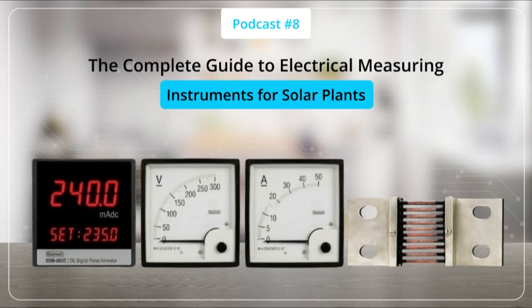To understand how much sunlight is actually available at a site, a pyranometer is used. It measures solar irradiance, the intensity of incoming sunlight, which directly affects how well the system should be performing at any given moment. Cable and system insulation safety is checked using an insulation resistance tester, often called a megger. This is critical both during installation and as part of ongoing maintenance. Thermal imaging cameras add another layer of diagnostic capability. By detecting temperature patterns across panels and connections, they can identify hot spots and loose connections before they become serious faults. Watt meters and power meters track electricity generation and inverter efficiency in real time.